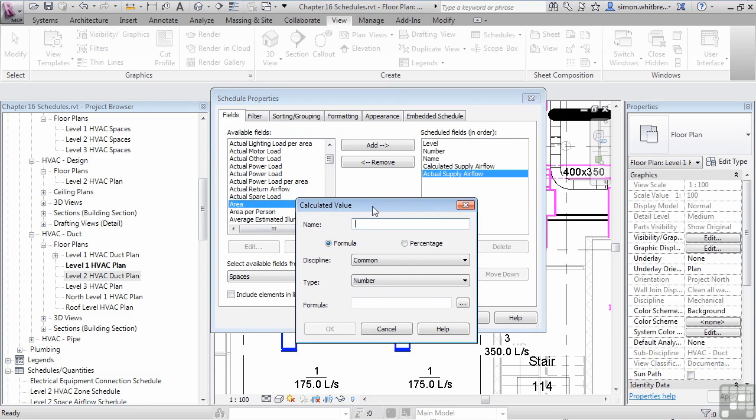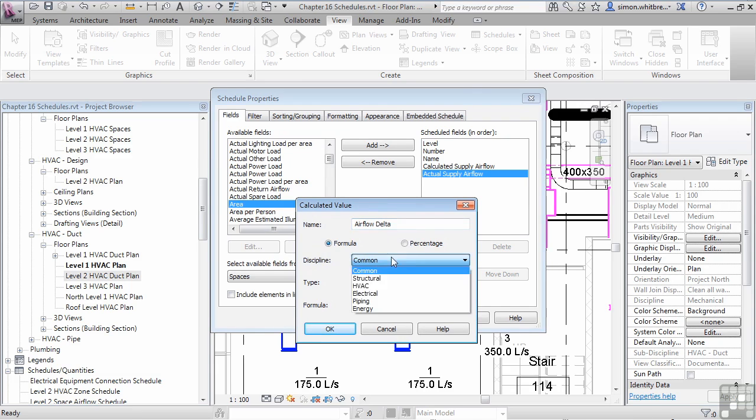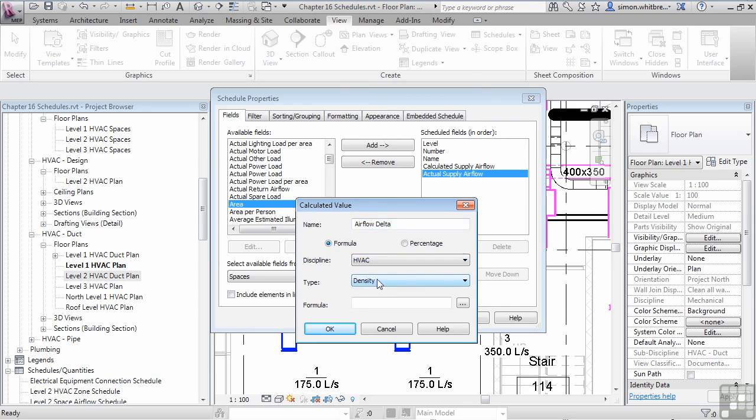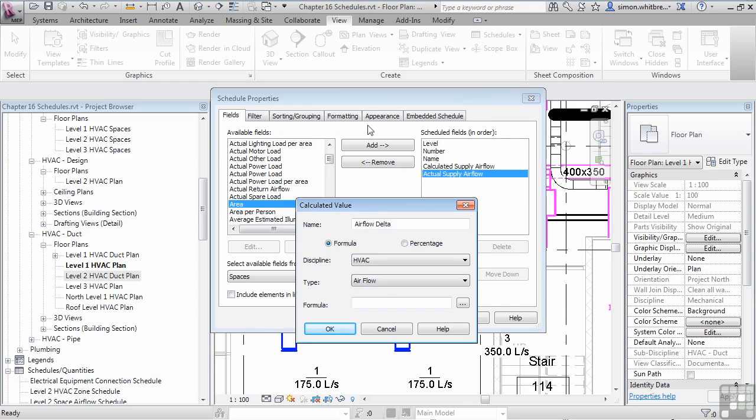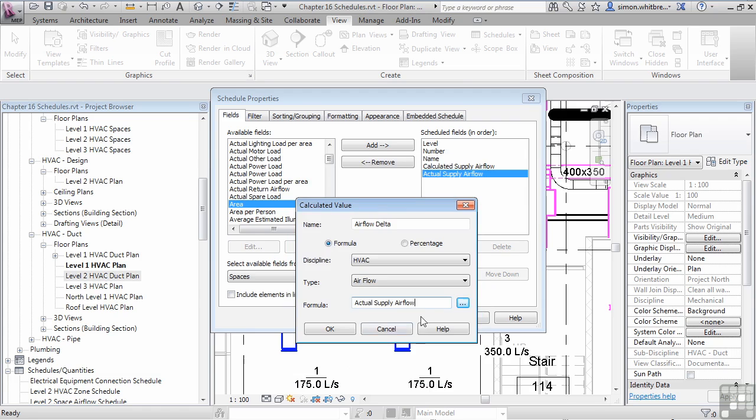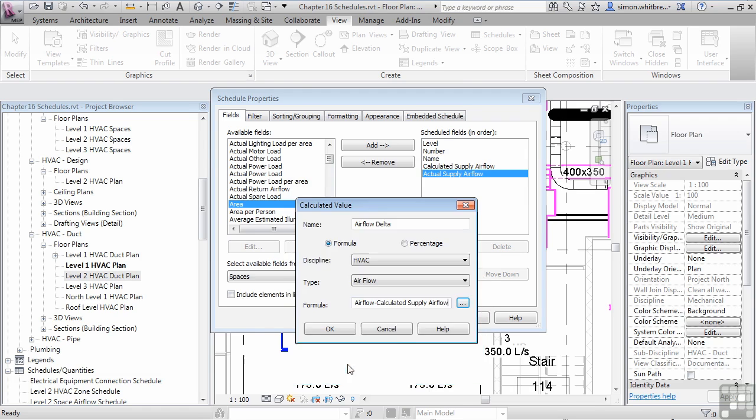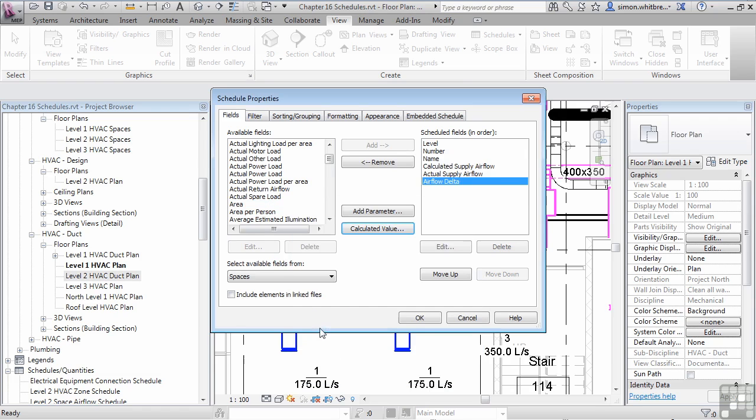And at this point, I am also going to create a calculated value. We will give this a name and let's call this Air Flow Delta. This is going to be a formula, the discipline of which is HVAC and it relates to air flow. And the formula is going to be my Actual Supply Air Flow minus my Calculated Supply Air Flow. And click on OK.